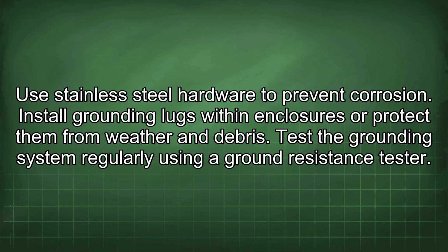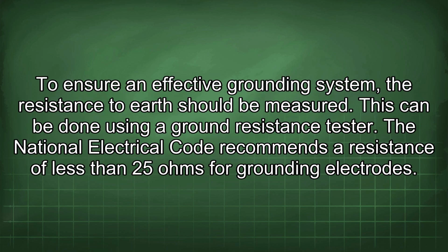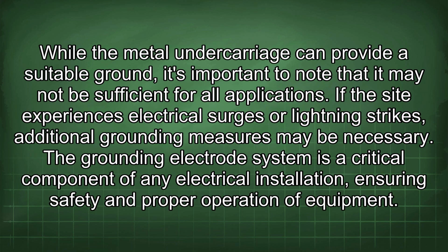Test the grounding system regularly using a ground resistance tester. To ensure an effective grounding system, the resistance to earth should be measured. This can be done using a ground resistance tester. The National Electrical Code recommends a resistance of less than 25 ohms for grounding electrodes. While the metal undercarriage can provide a suitable ground, it's important to note that it may not be sufficient for all applications. If the site experiences electrical surges or lightning strikes, additional grounding measures may be necessary.